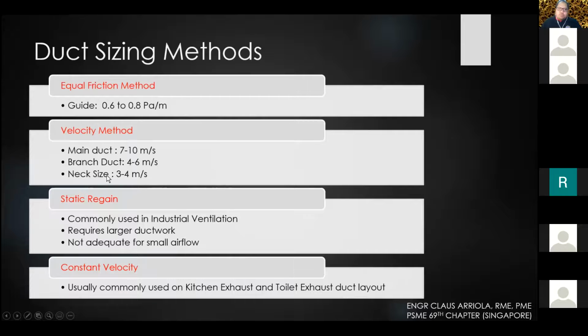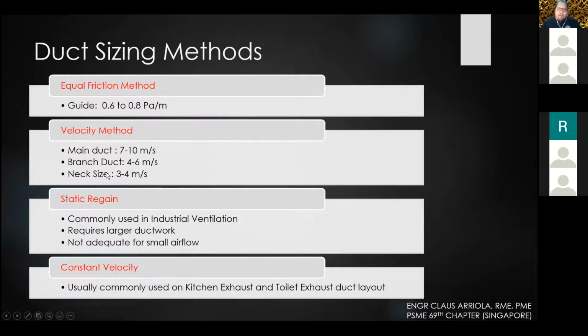Okay, we don't want very fast velocity, because with fast velocity there's a lot of pressure drop, which makes your fan very big. Then it will also affect the size of your genset. Be mindful that these fans are running in emergency mode. So it means the power will be supplied from the genset of your building.